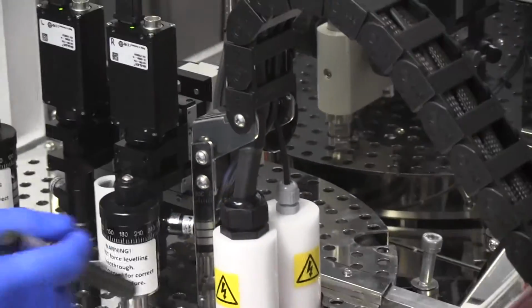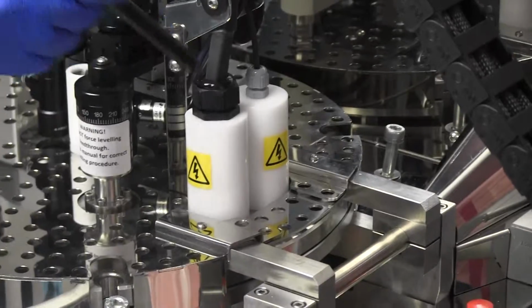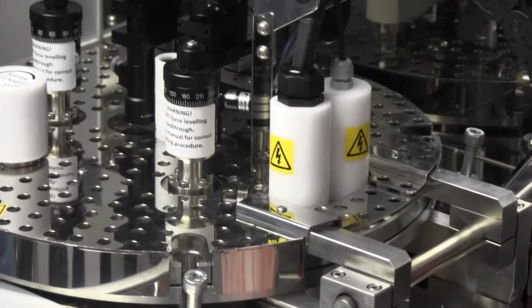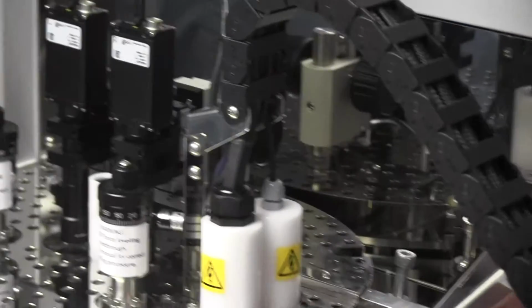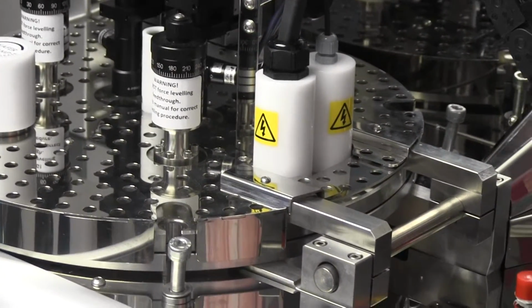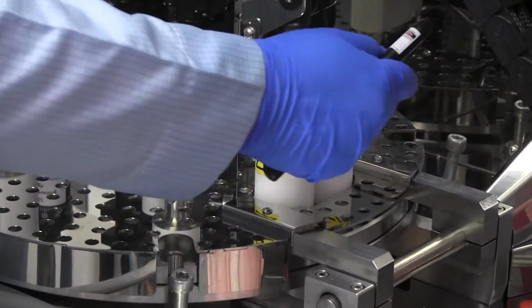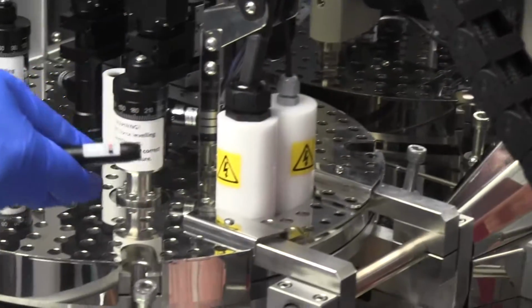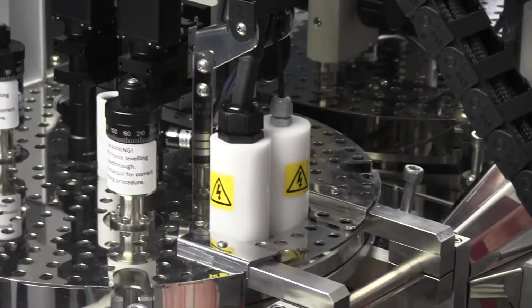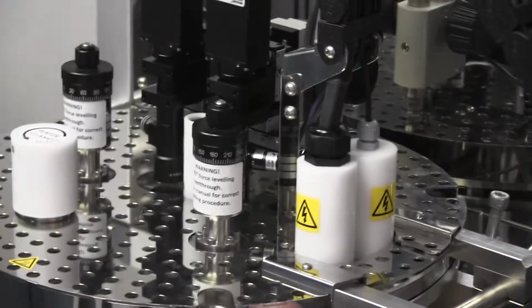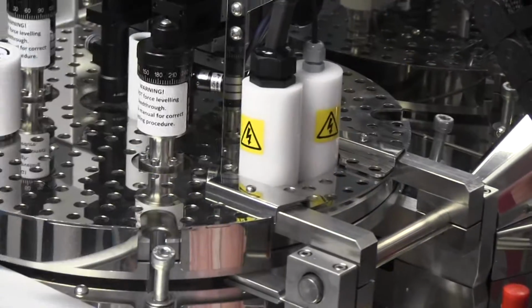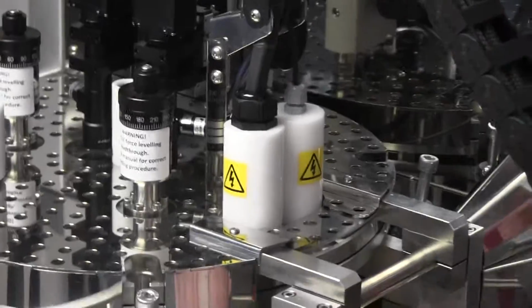And then lastly on the lid, we have these two feed throughs. This is the electrical feed through. This sends the power for the plasma, the power for the bonding voltage, and the power in and out for the upper heater. And in here is a thermocouple, so that's just for monitoring the temperature of the upper platen. All of those cables are fed through this chain and then they spread throughout the machine to wherever they need to go.